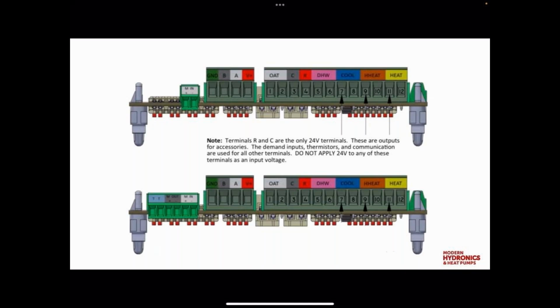John, I know you have a ton of experience in this field when it comes to dual fuel systems. Systems can get quite extensive when you're talking about boiler backups as far as the install cost and the space it burns up. Yeah, a typical install, we've seen a lot of them where you've got a separate circulator for the boiler and you have to have some type of hydraulic separation between that circuit, the circulator and the boiler and the balance of the system. And with this design, you've built that hydraulic separation right into the unit.